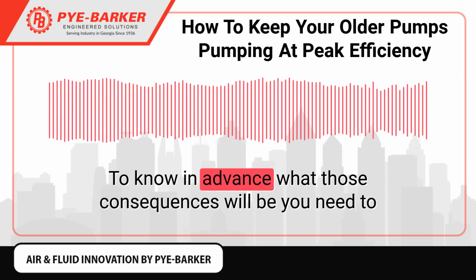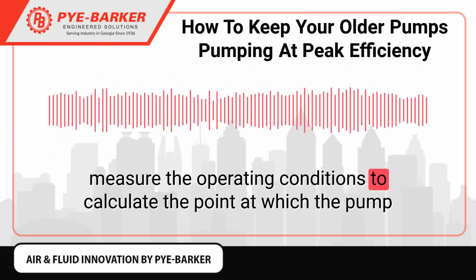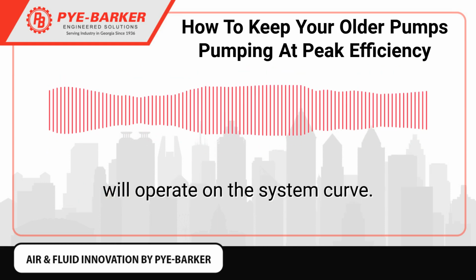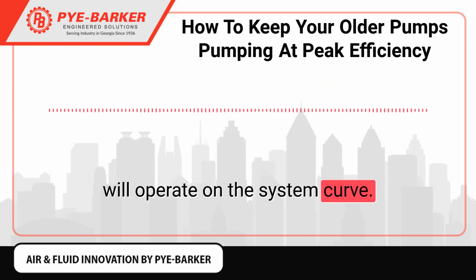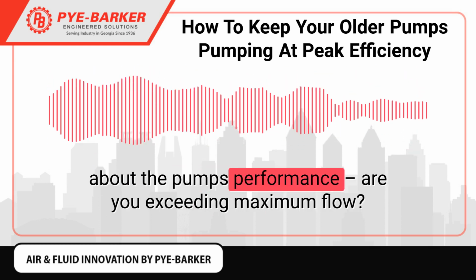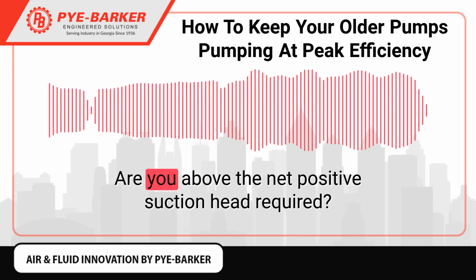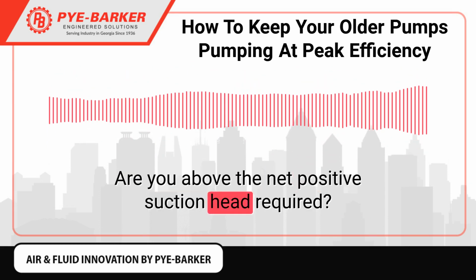To know in advance what those consequences will be, you need to measure the operating conditions to calculate the point at which the pump will operate on the system curve. Then you need to compare these with the original documentation about the pump's performance. Are you exceeding maximum flow? Are you above the net positive suction head required?